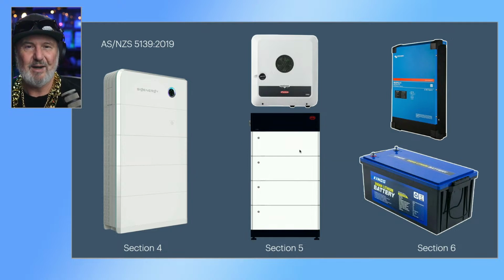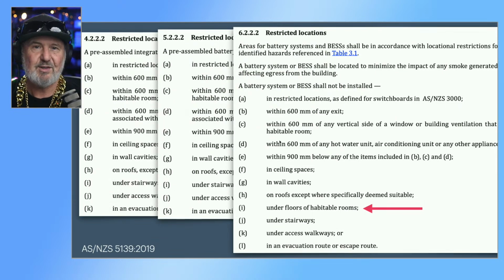Now, there's a bit of rankle about this Section 6 because some of the safest technologies end up in Section 6. Things like redox flow batteries, nickel chloride batteries, batteries that have no explosive gases or thermal runaway potential, but they don't have a product standard. And so when 5139 was written, we couldn't refer to a product standard for those chemistries and therefore put them into a safe category. So Section 6 is the catch-all for everything else. Unfortunately, some of the safest and some of the questionables all end up in Section 6. Now, the reason I'm going to so much trouble to tell you about this is because it relates to the next slide, which is restricted locations.